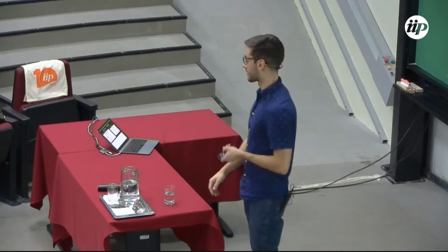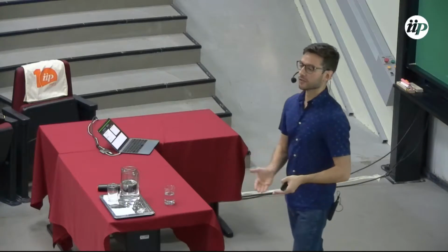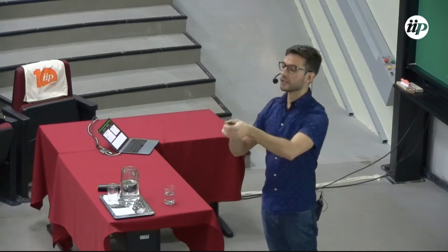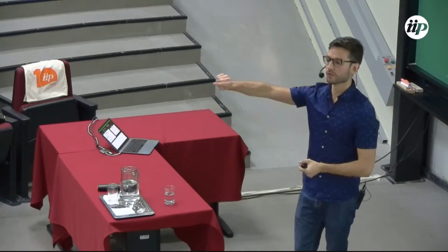These machines are extremely complicated, and it's not straightforward to actually say how that happens. So calibration is a complex and quite interesting process, but the bottom line is that to actually know what your instrument is doing, you have to put in a known input, look at the output, and then renormalize, if you wish. If you know what kind of strain you're putting in, so you push the mirrors a little bit by an amount that you know very well, and then you look at what output your instrument is giving you, then you can say, okay, this output corresponds to this much change in length over length, and so on.